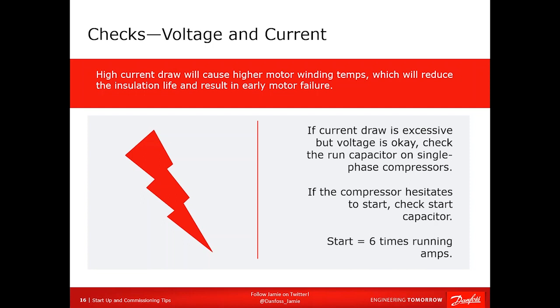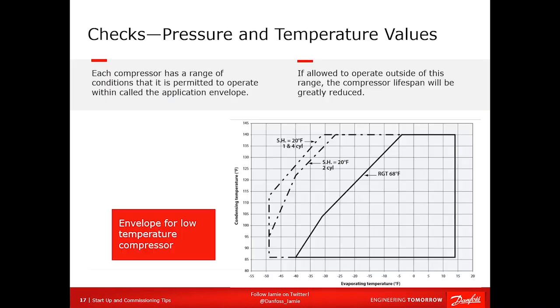Because remember, hesitation means it's drawing 6 times its normal current, which means you can rapidly overheat that compressor. I mean, very, very quickly. And it takes time to cool down. So a combination of short cycling and lazy starts will kill a compressor very, very quickly. So 2 things to look out for when you're starting up.